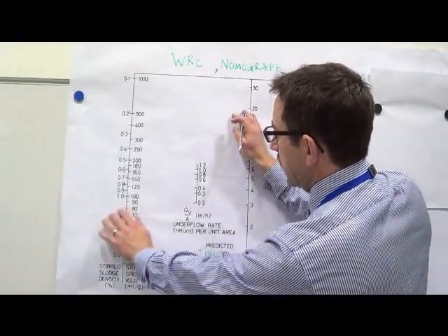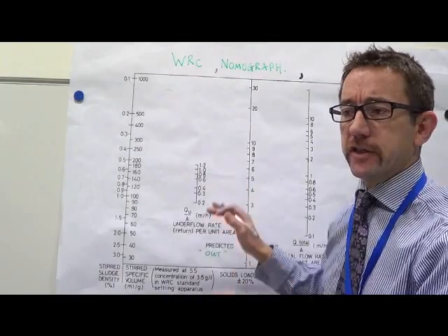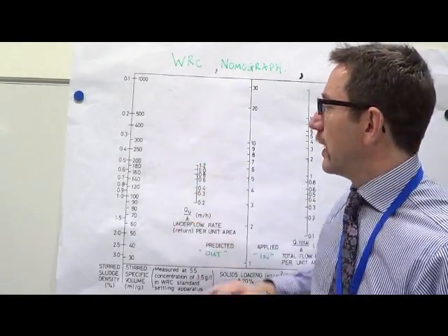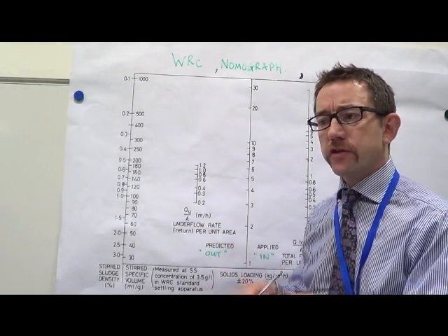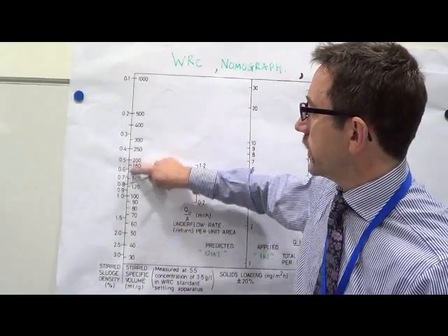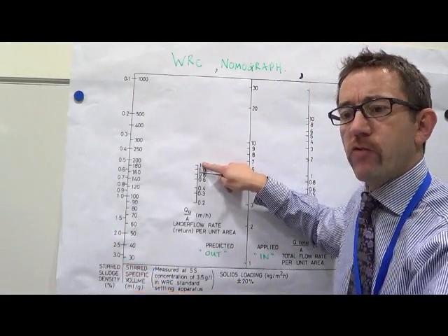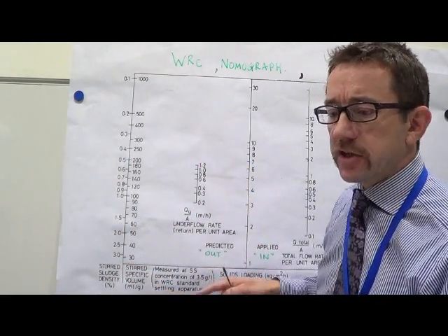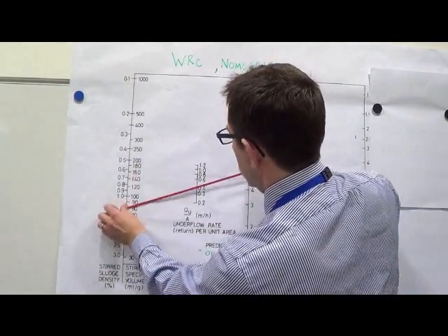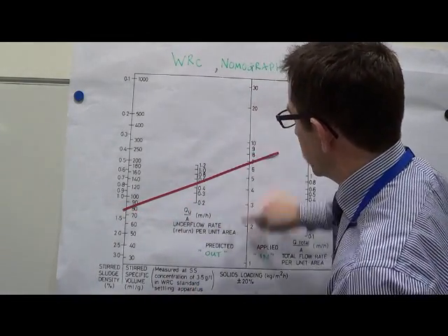And it is a game of two halves. On this half here, this is all about how much solids your final tank can take to the bottom and get out of the system. So this is about the capacity of your final tank to settle solids. And therefore you shouldn't be surprised to know that the things on there are the SSVI, the Stirred Sludge Volume Index, and also the underflow rate in terms of your RAS return. And all this does is a bit of a dot to dot. So for a given SSVI and a given underflow rate, it says your tank is capable of getting rid of that much solids.